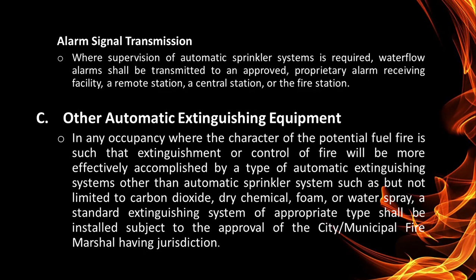Next is the other automatic extinguishing equipment. In any occupancy where the character of the potential fuel fire is such that extinguishment or control of fire will be more effectively accomplished by a type of automatic extinguishing system other than automatic sprinkler systems, such as but not limited to carbon dioxide, dry chemical, foam, or water spray, a standard extinguishing system of appropriate type shall be installed subject to the approval of the city or municipal fire marshal having jurisdiction.